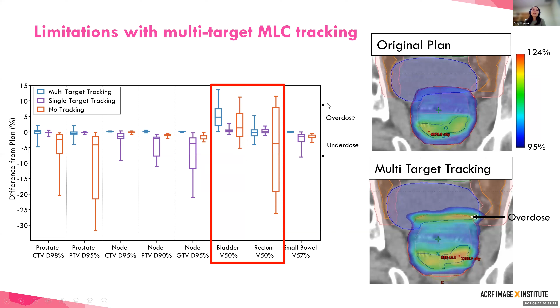Another technique that can be used for MLC tracking is to actually combine it with other real-time adaptation methods. So one of the main limitations that we have with MLC tracking is that we of course are working with finite MLC leaf width. So all of the motion that occurs perpendicular to the MLC leaves can't necessarily be corrected for, since we're again just working with MLC leaves that can either open or close.